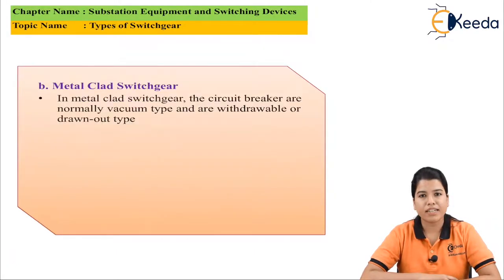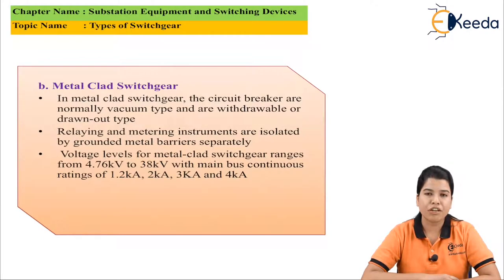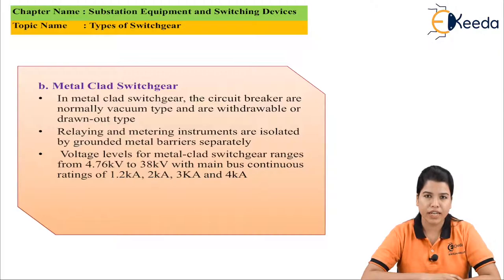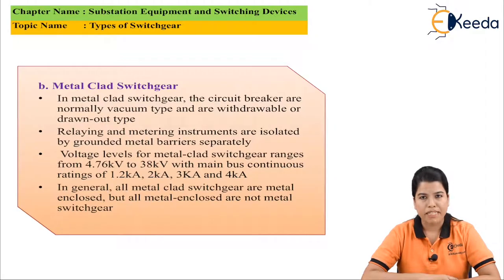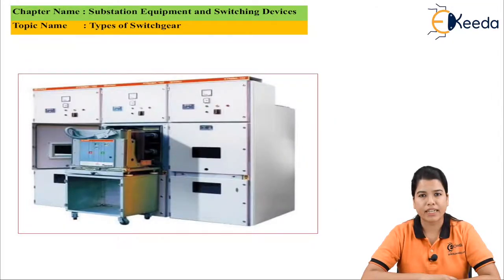In metal clad switchgear, vacuum type circuit breakers are used which can be removed outside the metal box. The relaying and metering instruments used are basically grounded. The voltage level for metal clad switchgear is 4.76 kV to 38 kV and the main bus continuous rating is 1.2 kA, 2 kA, 3 kA, and 4 kA. All metal clad switchgear are metal enclosed switchgear, but not all metal enclosed switchgear are metal clad switchgear.